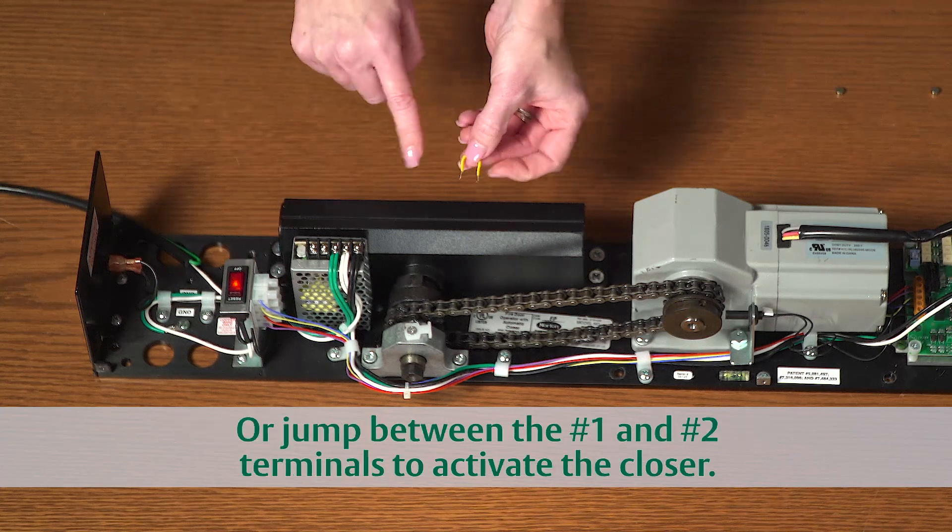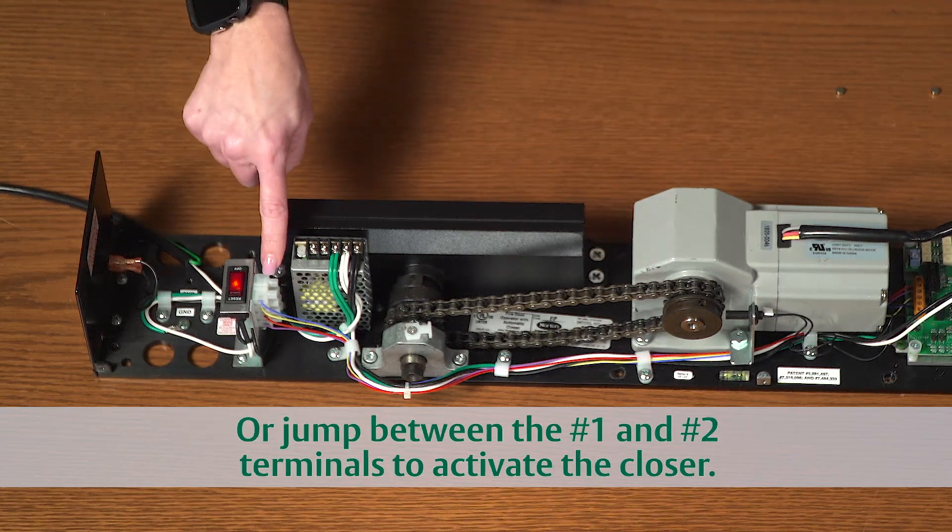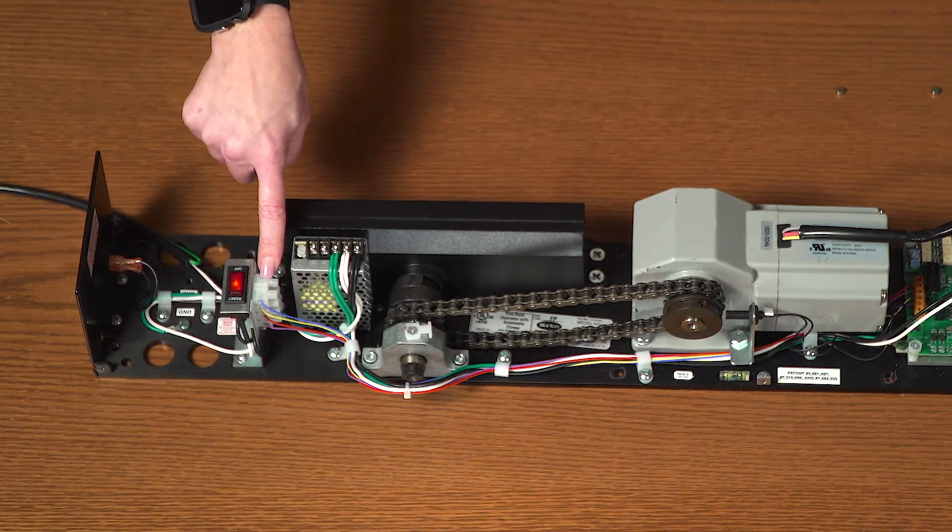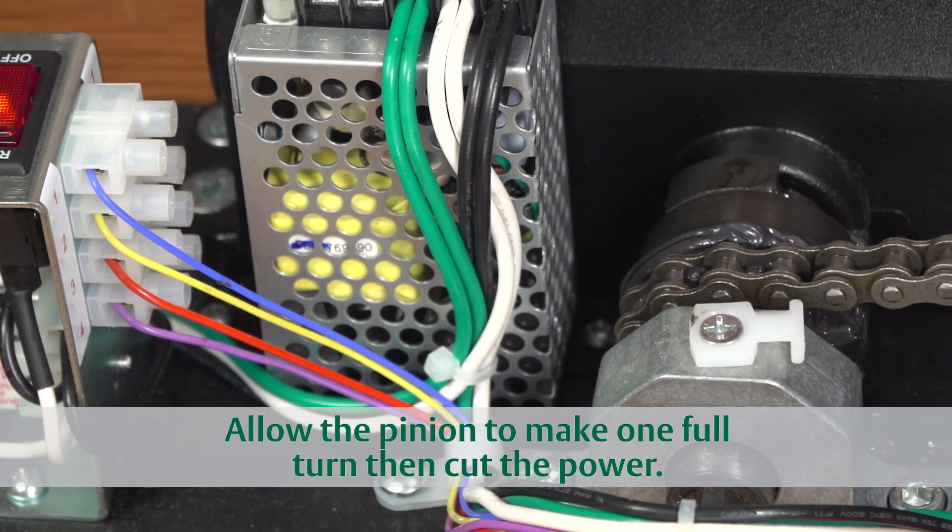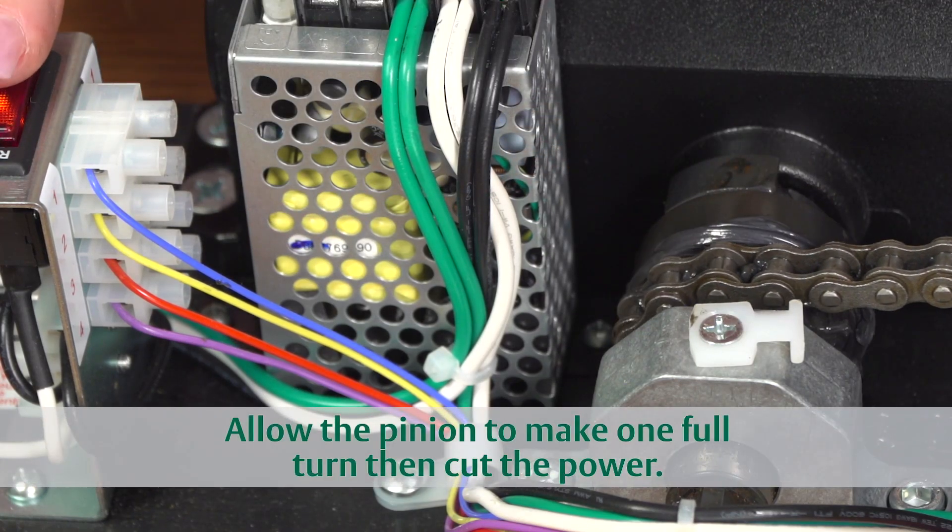If not, take a small jumper wire and jump between the number one and number two terminals on the connection block. Watch the cog as it turns and stop the operator when it makes one full rotation.